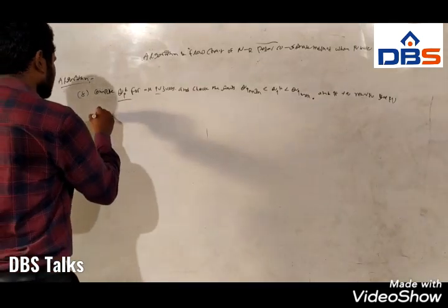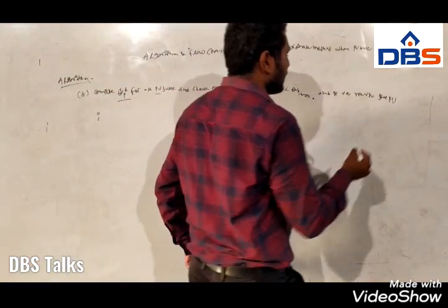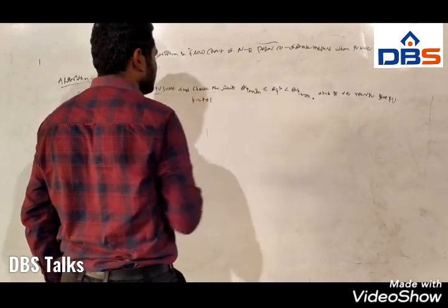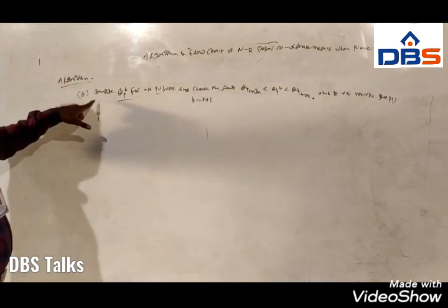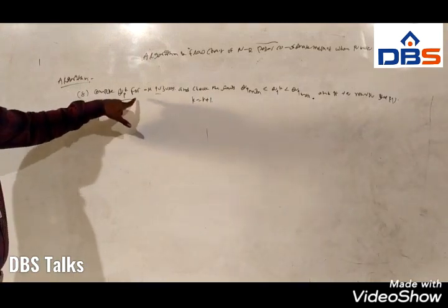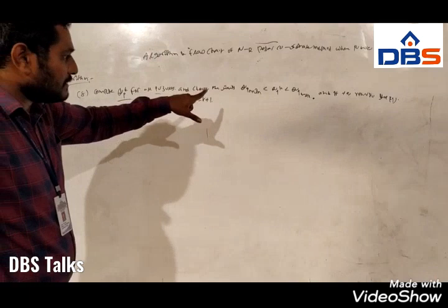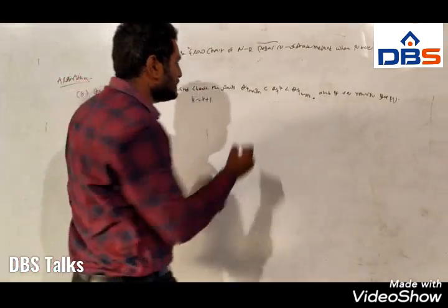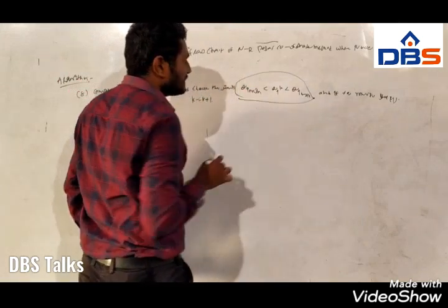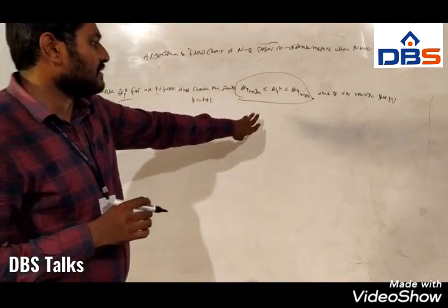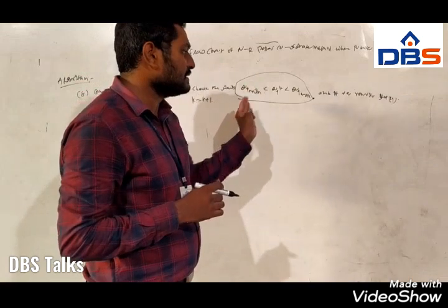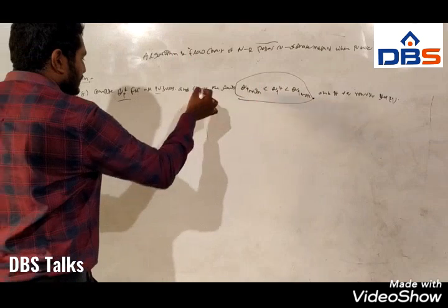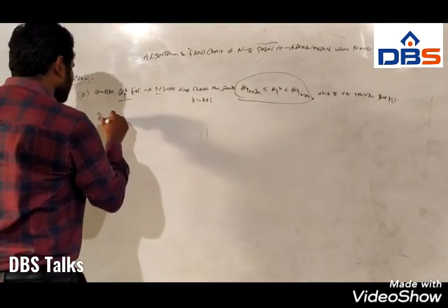And after that we have to increment the iteration count, that is K equals K plus 1. So in the eighth step we have to compute reactive power for all PV buses and check the limits, that is QP minimum less than QP^K less than QP maximum. That is the limit checking condition for reactive power in the PV bus, and if it is yes, we have to return to step 4 and increment the iteration from K equals K plus 1.